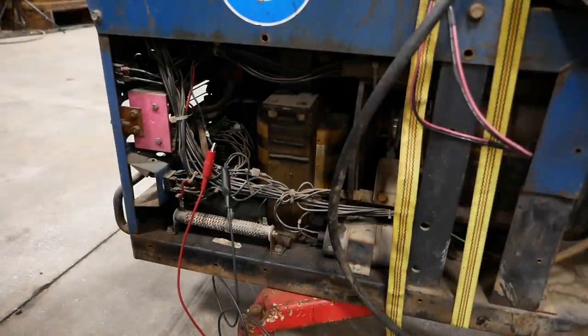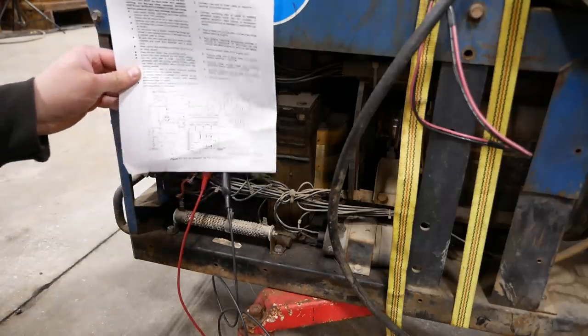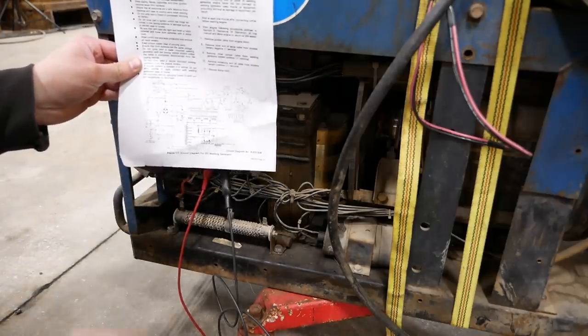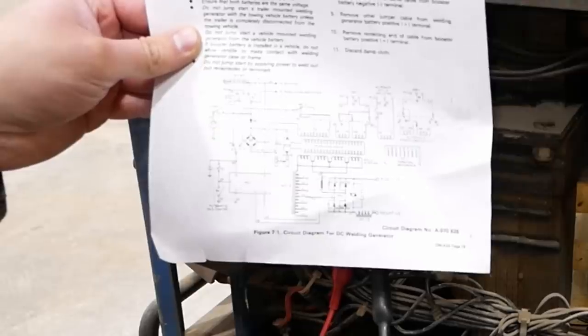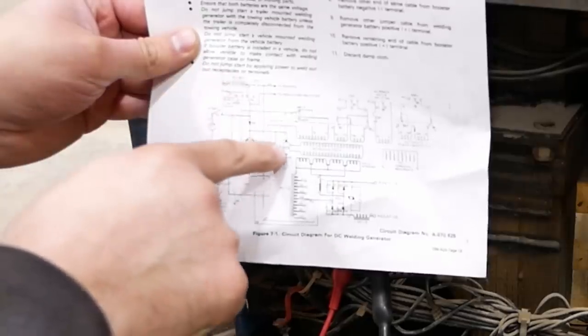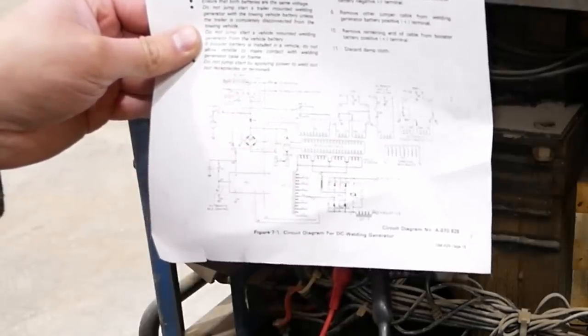Well, shucks. I feel like we're getting closer, but we're definitely not there yet. We just don't have enough output. And I think that's probably because we don't have enough input. So I think there's still just not enough excitation voltage or current to generate enough output. So I think we've got the 12 volt excitation to get it started, but it doesn't seem like it's taken over.